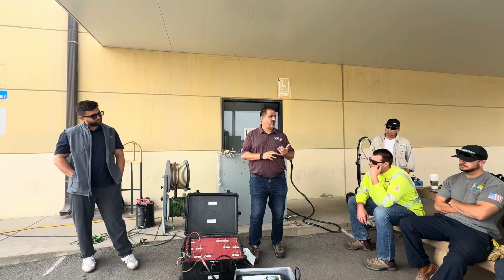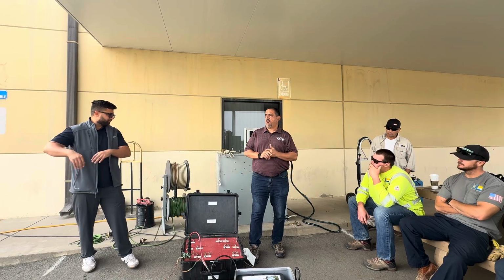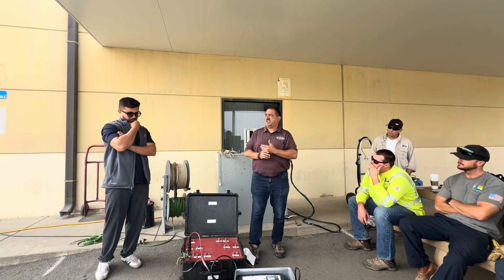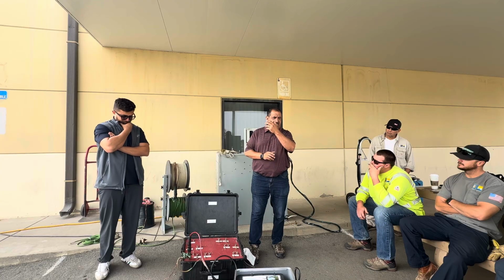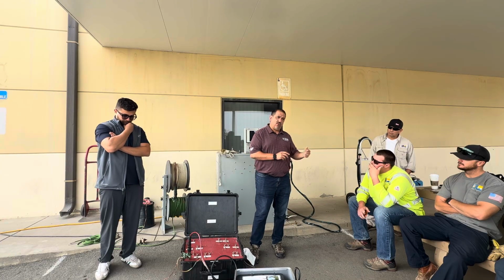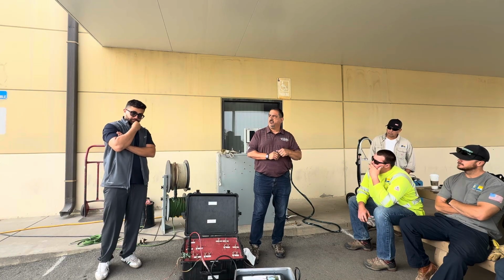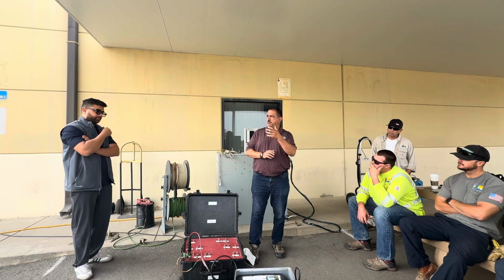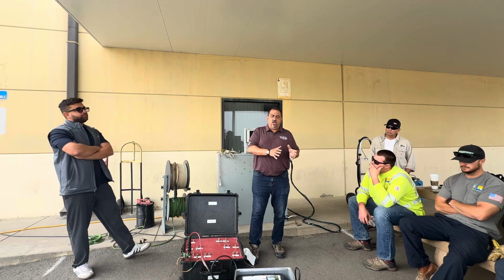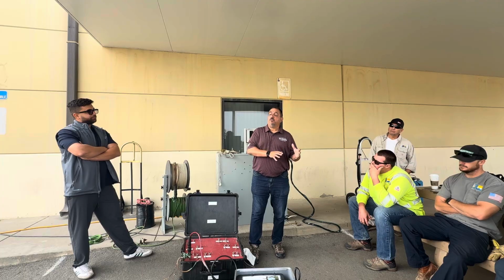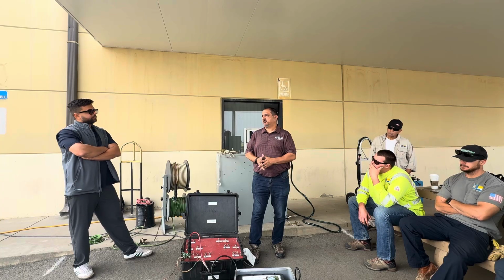A couple things are going to control your radar. One, I'm on the neutral of the cable that I'm testing. Two, I'm 6 to 8 inches away, and I take that connection point and I clean it. Take your wire brush out, get all that dirt and debris off of there so you have a more solid connection, because the more things that get in the way of that, it's going to affect what your radar picture is going to look like.